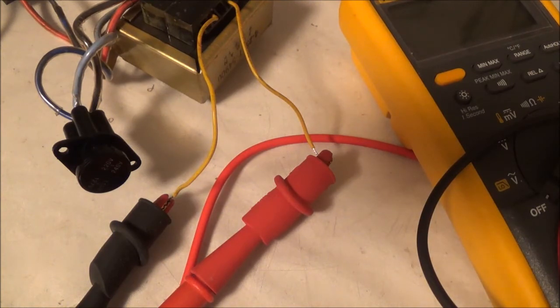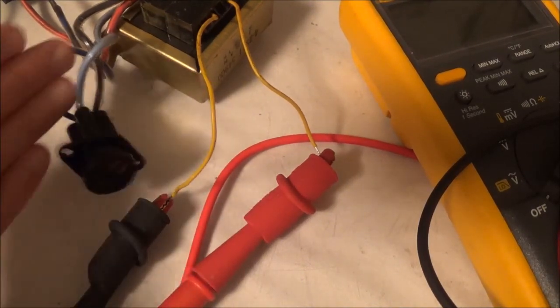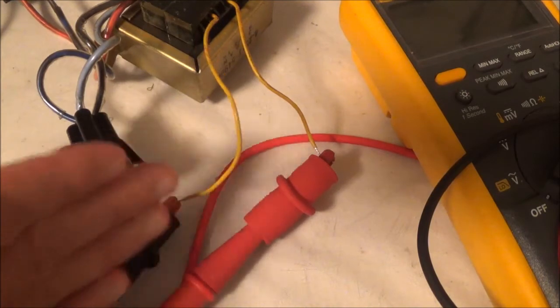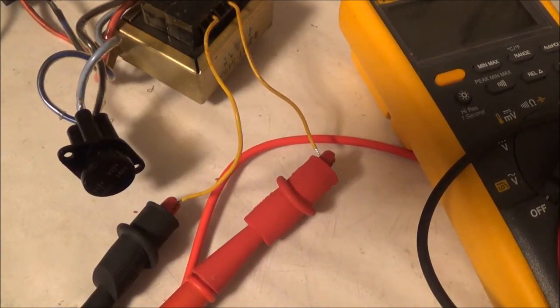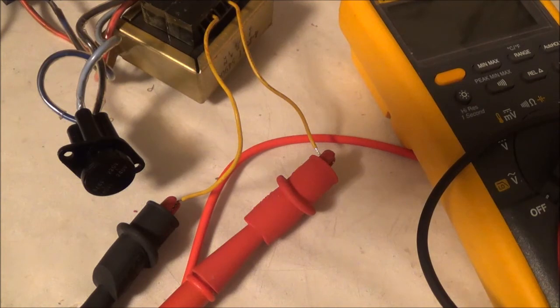Well, I think I really don't have anything else to add, except that if you want to replicate this test, I think you would have to measure the voltage of your source, what's coming into the primary side, not secondary, and that it's going to be an AC voltage. Whether it's a variable isolation transformer, variac, or audio generator, your voltmeter's got to be hooked up to that, and that way you'll get an accurate reading. I think I was somewhat thrown off initially because the meter on my variable isolation transformer seems to be not very exact, so that gave me the wrong ratio.